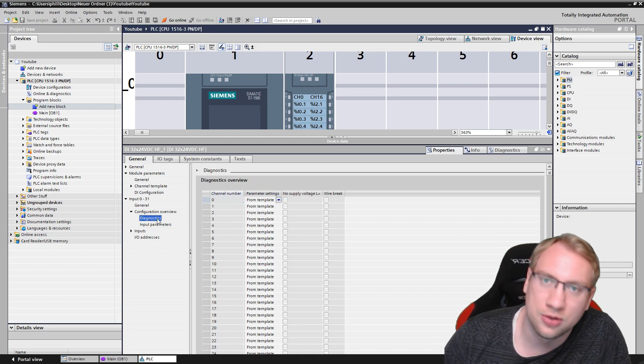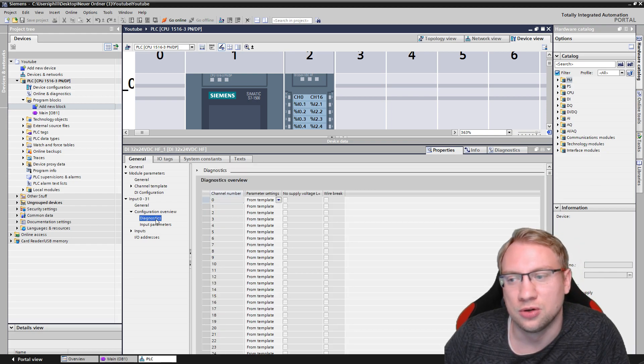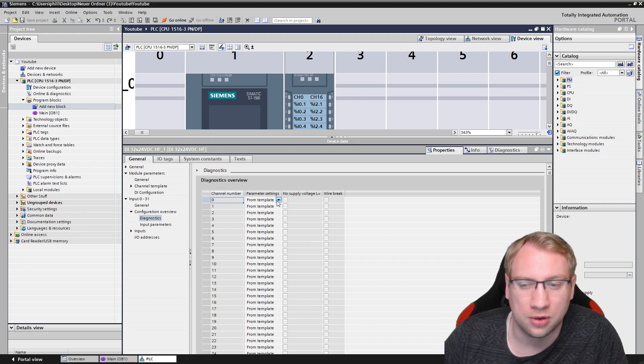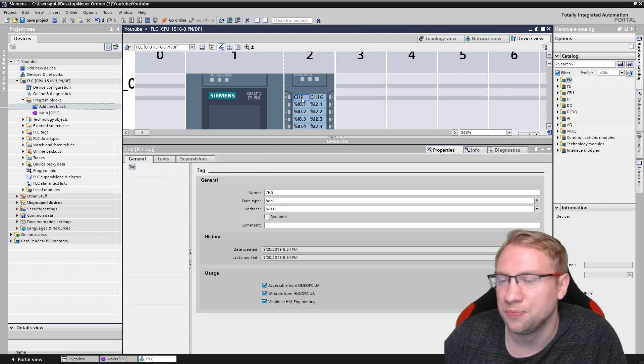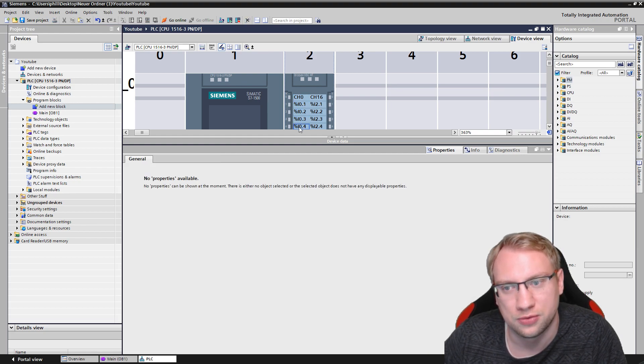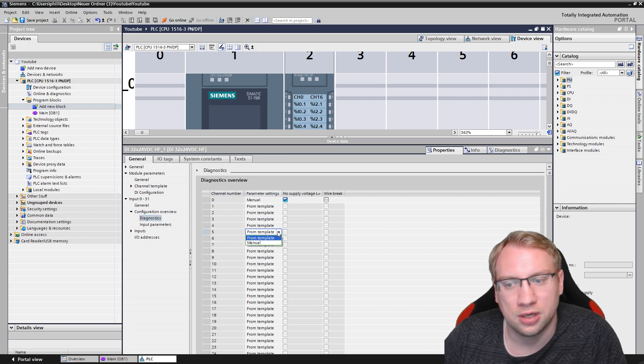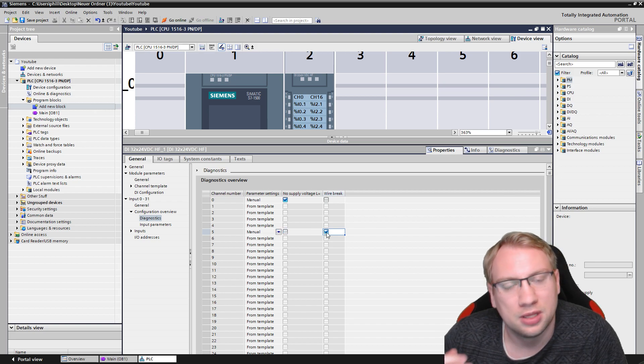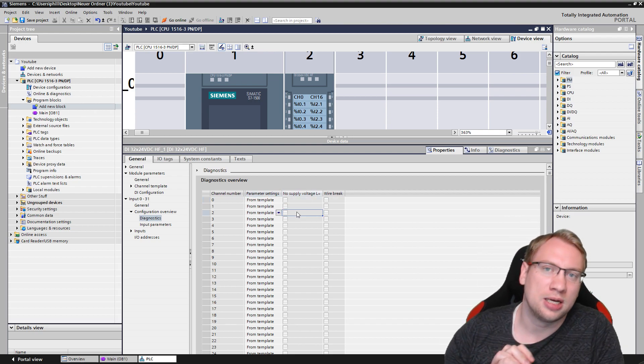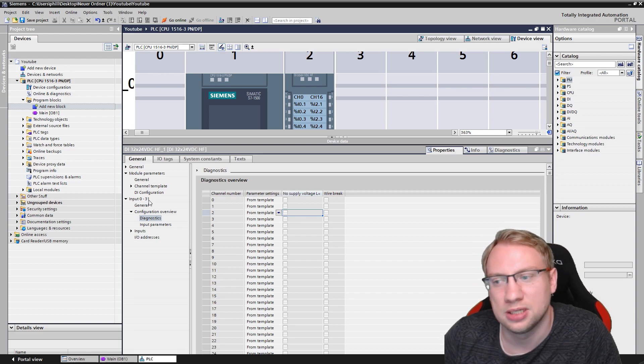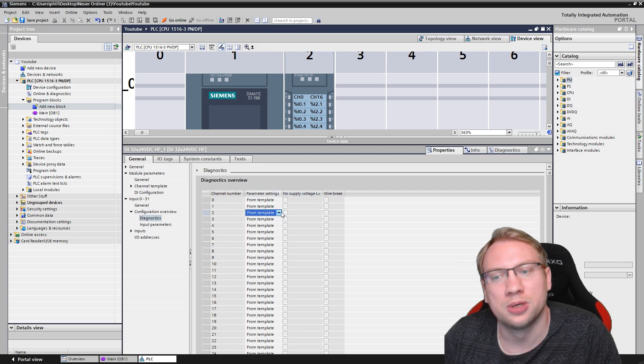There's also a diagnostics overview of all channels, so I don't have to go and scroll through everything — I can just go to the diagnostics and here we see for each channel I can individually turn it on or off. If I want to do it manually, I can turn it to manual and say for channel zero — this is channel zero, channel one, two, three, four, then channel 16, 17, 18, 19 and so on because I have so many inputs. I can do it manually for each one or take it from a template.